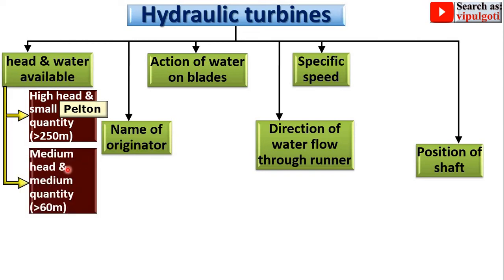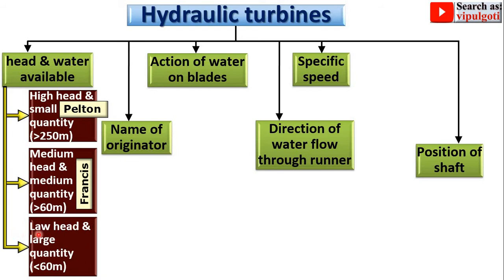Next, medium head and medium quantity: if the head is more than 60 meters, it is called a medium head turbine. The example is the Francis turbine. Next, low head and large quantity: generally a head less than 60 meters is called a low head hydraulic turbine. The best example for low head and large discharge is the Kaplan turbine.